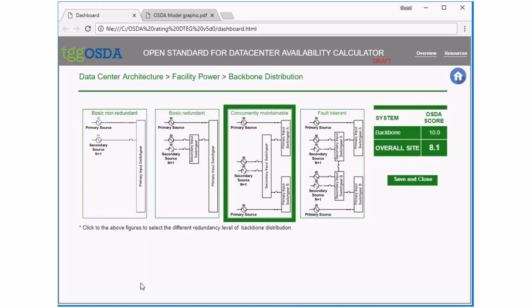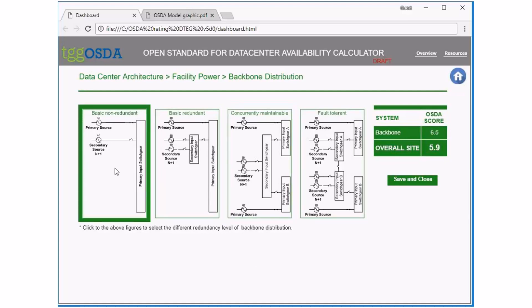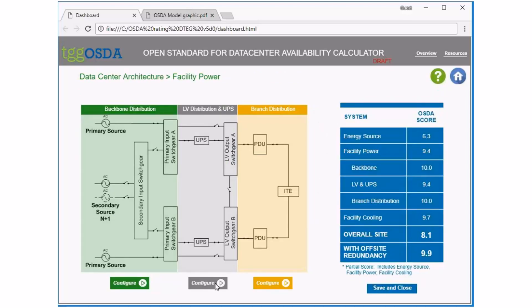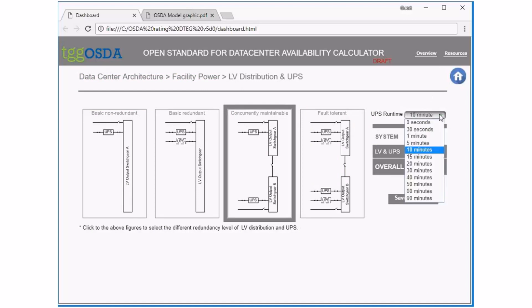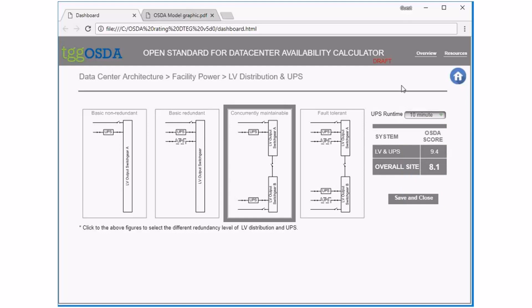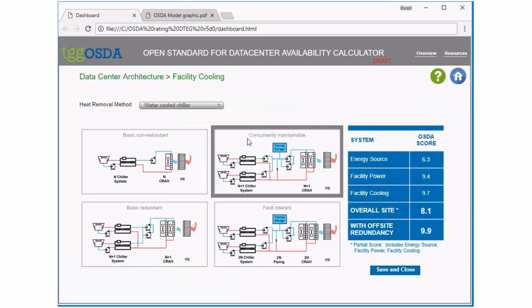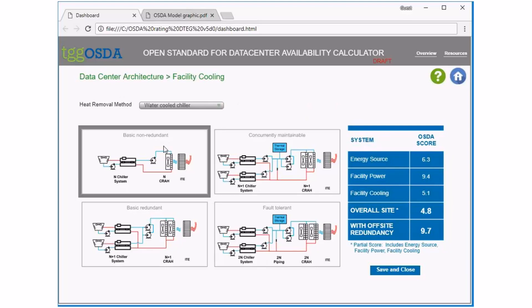Let's look at the facility power module. We've broken up the electrical distribution into three major sections: backbone distribution, which is where your input substation and primary switchgear happen; low voltage distribution with the UPS; and branch distribution. Pretty traditional architectures are all we have modeled right now, but you can go into each one and change them. The concurrently maintainable design is defaulted, but you can select basic non-redundant and see the score on the right change and its effect on the overall site score. In low voltage distribution you can also change the runtime of the UPS — it's interesting to see how that changes the overall site score, especially with a lower-quality utility grid or a non-redundant generator system. Branch distribution covers options like two-corded devices and single-cord devices.